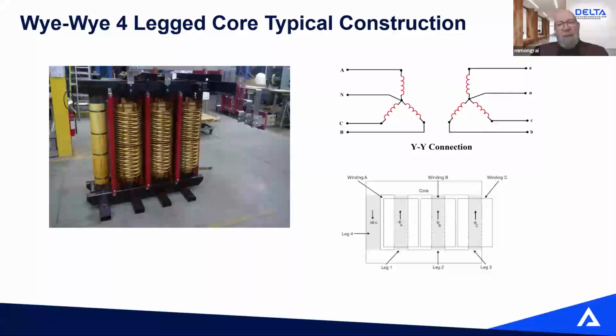I've been talking about YY and 4-legged core. This is a picture that's been taken at our plant a few years ago. So that's a 5 kV class YY 4-legged core. As you can see, you have your typical 3-phase, phase A, B, and C mounted on the 3 legs of the core. But on a 4-legged core, what we do is at the end we bring a 4th leg, and in the case of a 5-legged core, we have the same leg at the other end. So it's a core leg, fully laminated, but there's no winding dropped on that leg.